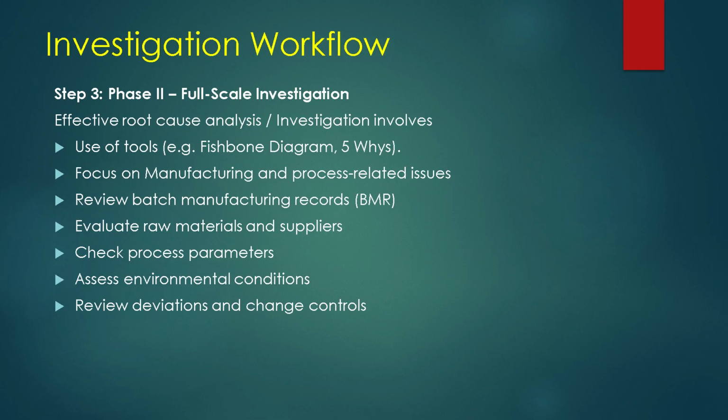Step 3. Phase 2 full-scale investigation. This phase involves a comprehensive root cause analysis using tools like fishbone diagram and 5 whys. The investigation focuses on manufacturing and process related issues, including a detailed review of batch manufacturing record.